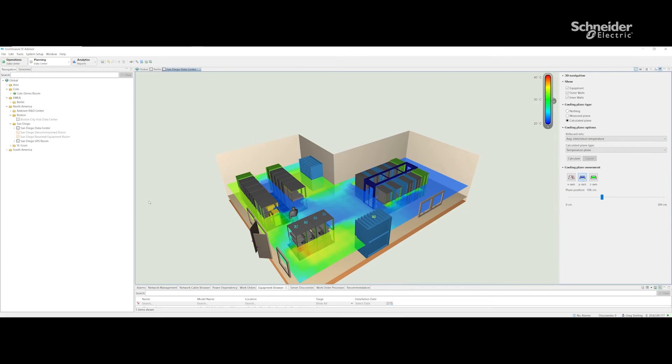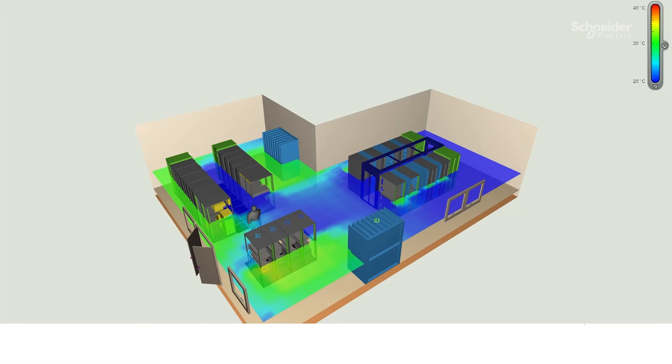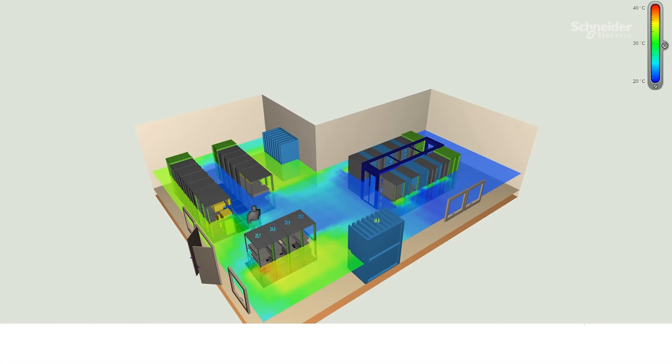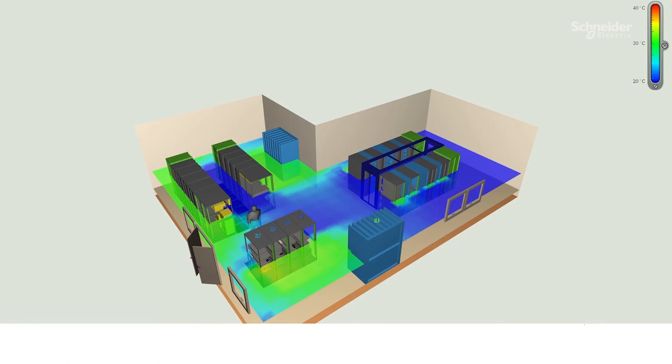Let's compare these two different views of the same room. Here is our room with 20 degrees supply temperature. If I change the temperature to 22 degrees, the change is minimal. We can see that based on the colors around the racks, in the front and back of the racks. Let's go back to 20 degrees—the temperature is a little bit lower, so we see this dark blue color here.